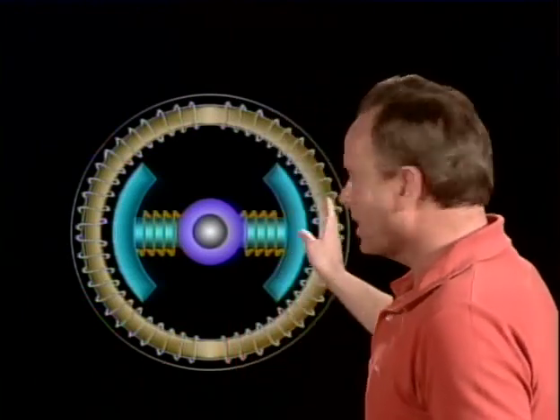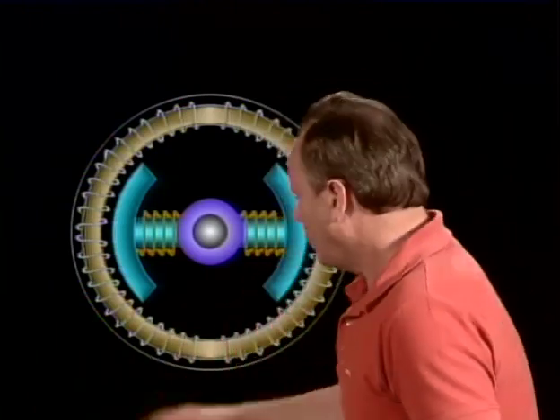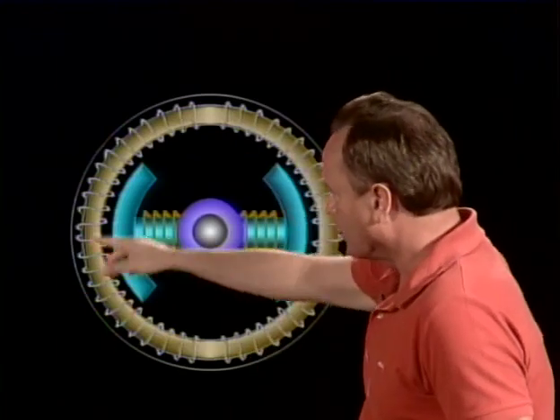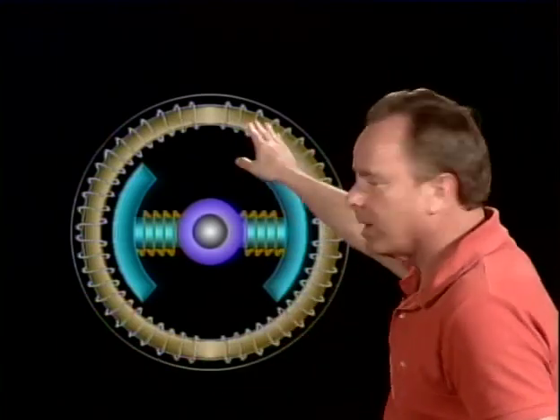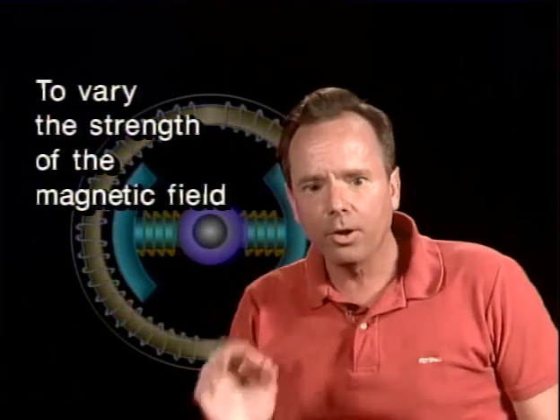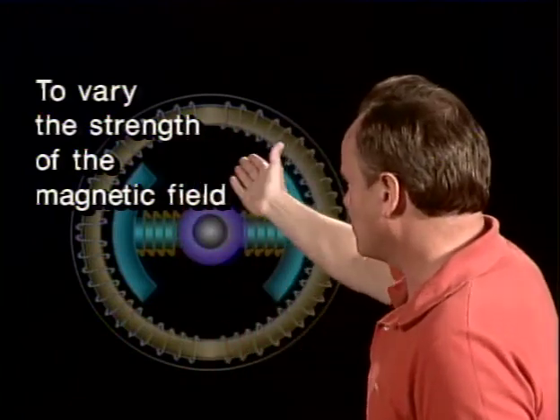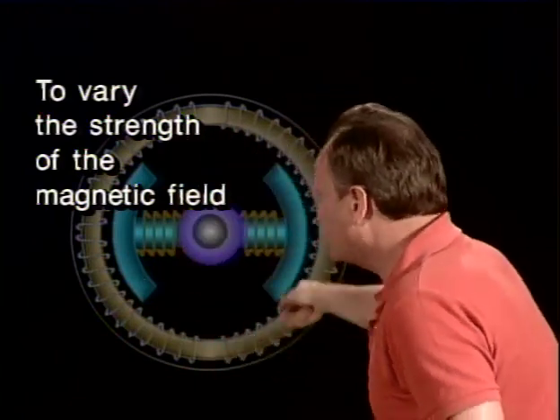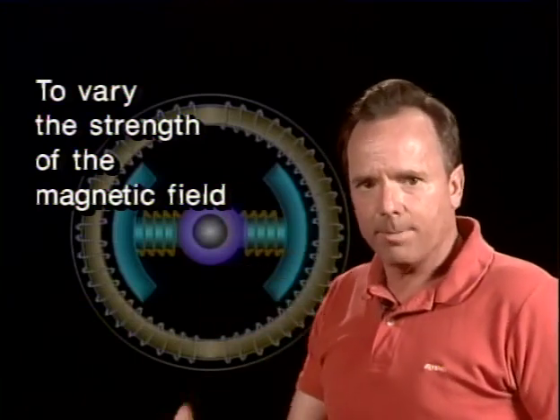And the field assembly is very important. It's essential to the motor or generator. It's got to be there. Now, the only practical method of maintaining a constant voltage output from an aircraft generator under varying conditions of speed and load is to vary the strength of the magnetic field. So the regulator varies the strength of this magnetic field. And that's the way you change the output of the generator or keep it constant.